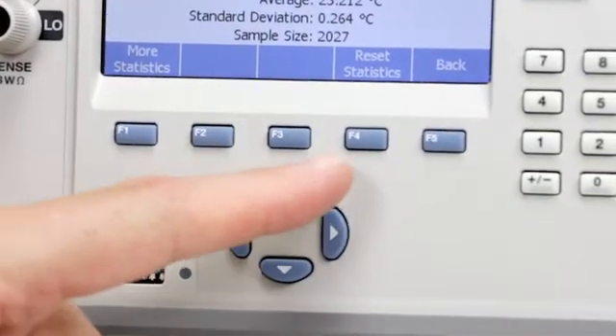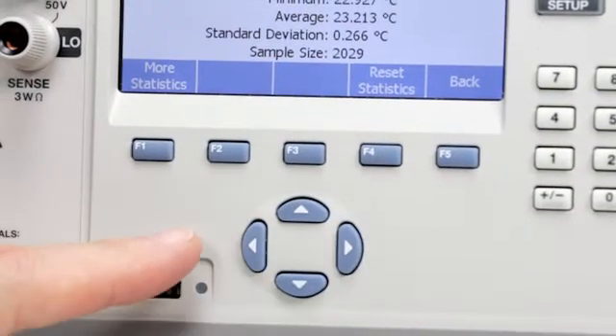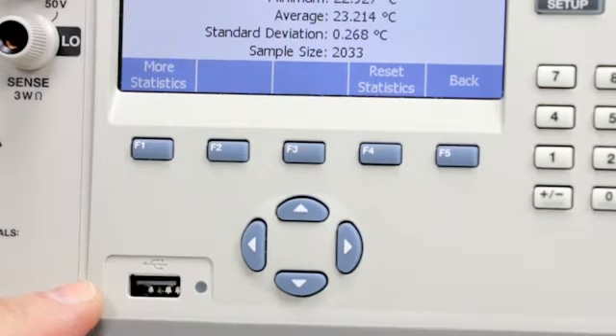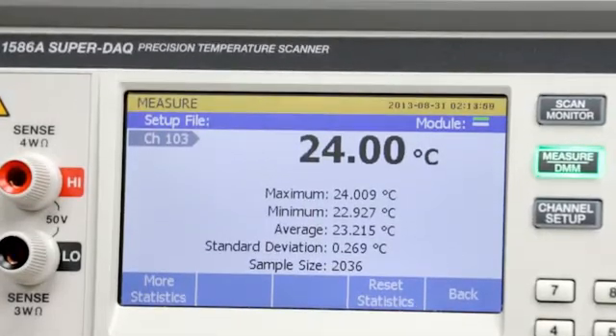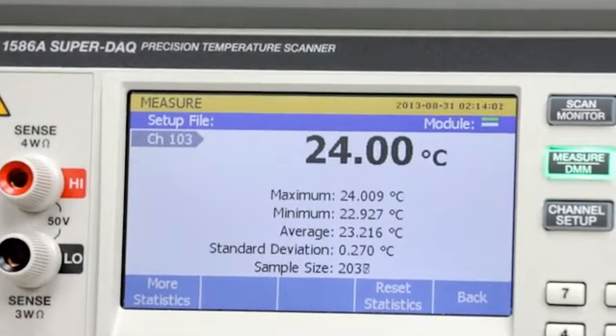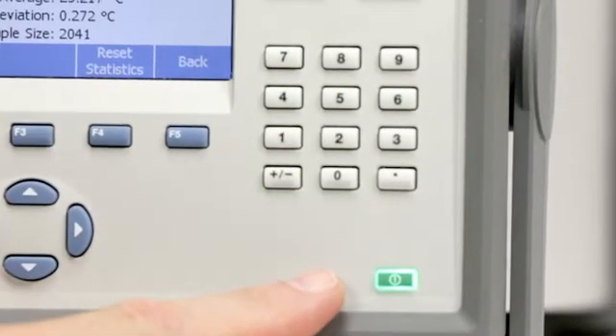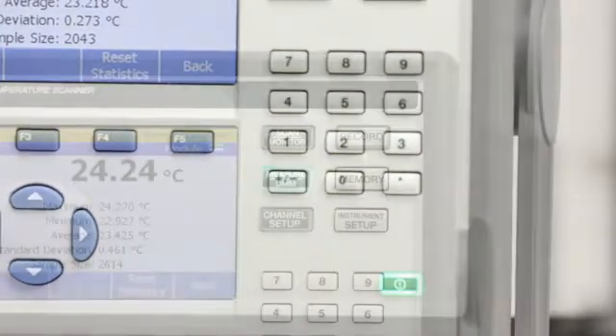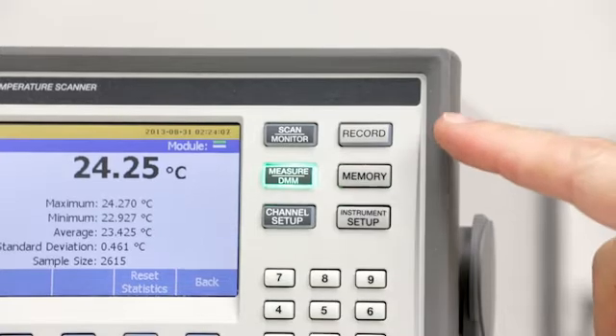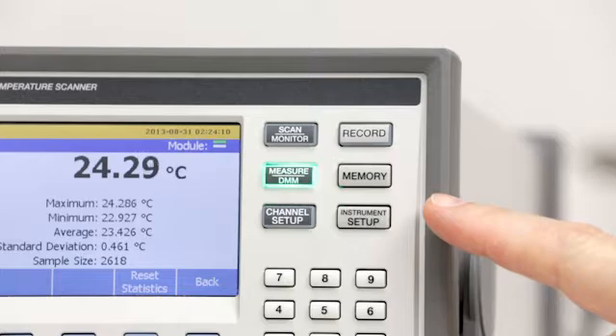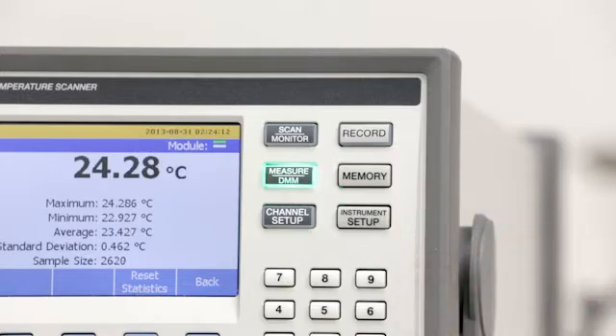There are function keys for soft menu selection and navigation, a USB port to copy and move your data and setup files, a color display with channel status indicators, a numeric keypad for entry and a standby button. The main buttons on the 1586 are the six buttons in this group. You'll notice that they are backlit so you always know where you are and the recording status.